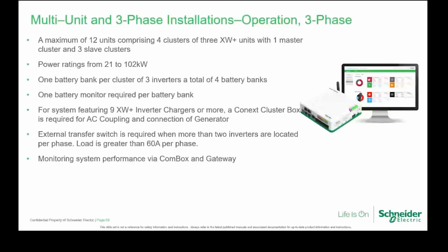You can find them on the XW Plus website. You can download those documents if you're going to do a multi-cluster installation. You're also going to require an external transfer switch when you have more than two inverters per phase, because they become greater than 60 amps per phase. That's the maximum power rating of the transfer switch inside the XWs. So if you're getting more than 60 amps per phase, you're going to need an external transfer switch. You can monitor the system from the ComBox or from a new Conext Gateway. The benefit of having the Conext Gateway is that you've got remote access to the system to make any configuration changes.